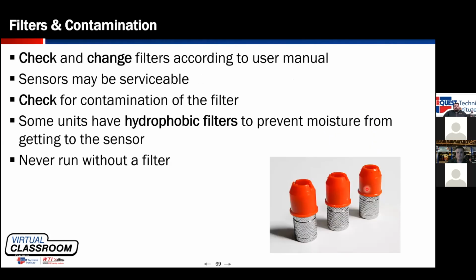There is maintenance that has to be done on leak detectors. There is a filter somewhere in that leak detector to keep moisture from getting into the sensor and to keep other nasty stuff from getting into the sensor. Periodically check that filter. If it becomes contaminated, replace it. These do have a maintenance schedule from the manufacturer that they are to be replaced every so many hours. The same thing goes for the sensing element on the leak detector. The sensing tip or sensor inside needs to periodically be replaced. Never run without a filter. There is a pump inside of that leak detector. That's part of what you hear running when the detector is running. You don't want to suck something into that leak detector without a filter on the tip.